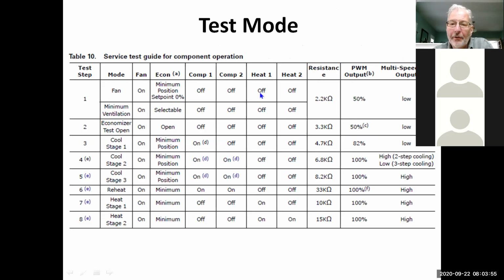On the newer units, when you go to test 1, it's going to be fan, okay? Test 2, economize. Test 3 is cool, stage 1, stage 2, stage 3 if it's available. Reheat if it's a dehumidification unit, and then heating 1, heating 2. Now, everyone's a little different depending on the configuration. If it's only a single compressor unit, you're only going to get 1 stage of test.